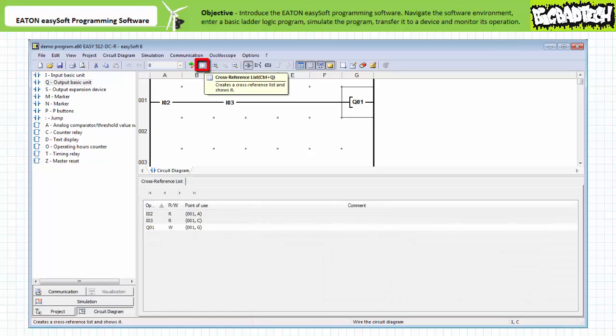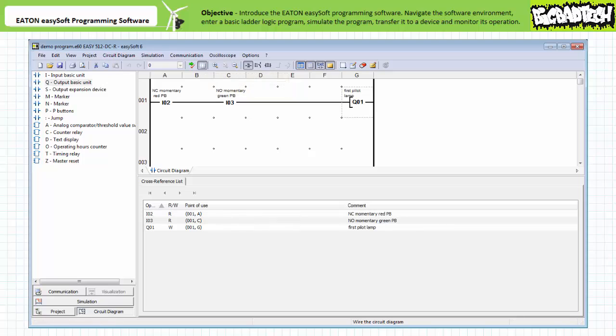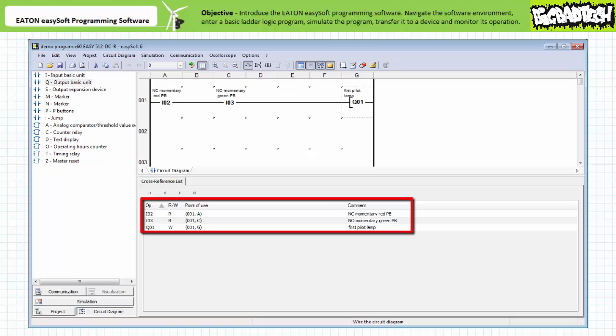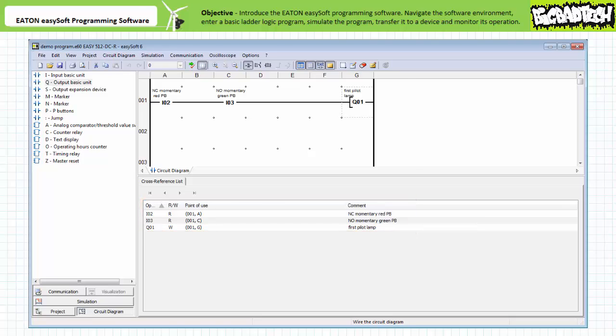Note the cross-reference list button produces a handy chart cataloging all contacts and coils utilized in the program and their rung and column address. This is an extremely handy feature for troubleshooting a larger program. One can also include comments describing the nature of inputs and outputs. I've included the comments: normally closed momentary contact red push button for input I2, normally open momentary contact green push button for input I3, and first pilot lamp for Q1. In addition to commenting each input and output, the add note button allows comments to be made about individual rungs. These comments are extremely helpful features in recommended work practices as our programs grow in size and complexity.